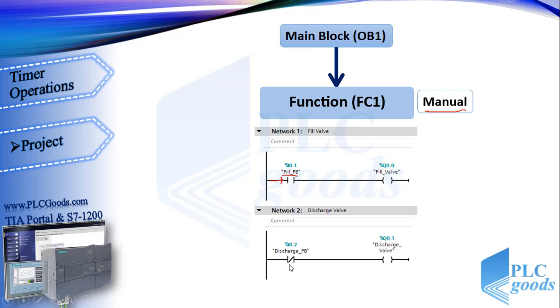Sometimes, based on the industrial process, we need to consider some safety conditions in our program. For example, suppose the fill and discharge valve cannot be on simultaneously. For this condition, a normally close contact of discharge valve is inserted in the first line.